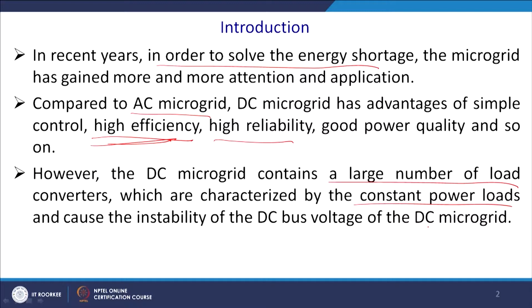One of the major problems of having a CPL in the system is that if the voltage drops, it will draw more current and take the system towards instability. Thus a large number of constant power loads causes instability of the DC bus of the microgrid.